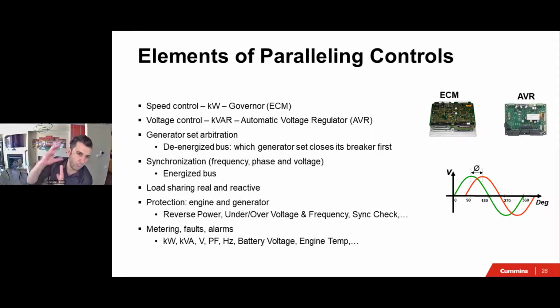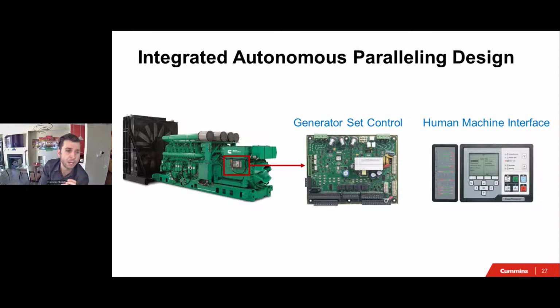So we looked at what we need to control, and then we looked at traditional design, how it's done, and now how is it accomplished in integrated autonomous paralleling: all the functions that I just described actually reside on one controller, on the generator set control. So here's a generator set with what's called a generator set control box, and inside of it there is this microprocessor-based control, and then there is the human machine interface, or the HMI. And the generator set control is responsible for doing all the paralleling functions that I just described.